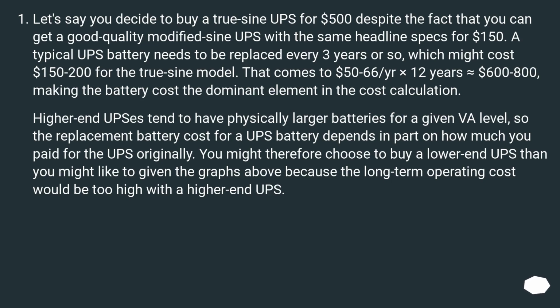Higher-end UPSes tend to have physically larger batteries for a given VA level, so the replacement battery cost for a UPS depends in part on how much you paid for the UPS originally. You might therefore choose to buy a lower-end UPS than you might like to, given the graphs above, because the long-term operating cost would be too high with a higher-end UPS.